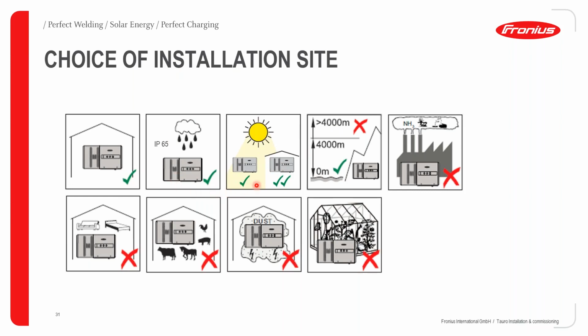What's really good on the Tauro is that we can basically install it in direct sunlight, and this is due to the double wall active cooling design that we have incorporated. With the Tauro, you can install it anywhere from 0 to 4,000 meters in terms of altitude. However, above 4,000 meters it is not suggested that you install it, because you can get a lot of derating above 4,000 meters above sea level.